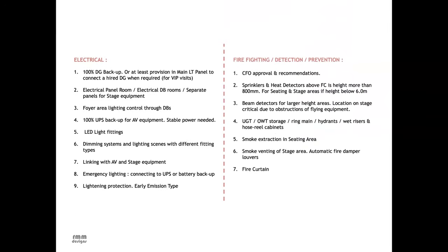Moving on to electrical, what you need to be aware of is your electrical system should be designed so that 100% DG backup can be given. A lot of places where there is a power issue, where the power supply is not very stable, you will need to provide the DG in any case. But places like Mumbai, where typically power is not an issue, a lot of people don't plan for this DG backup, but that is still essential, because if you have a high level dignitary visiting, like a chief minister or a prime minister, their security protocol states that no matter what the situation is, you need to have a power backup from a security point of view.